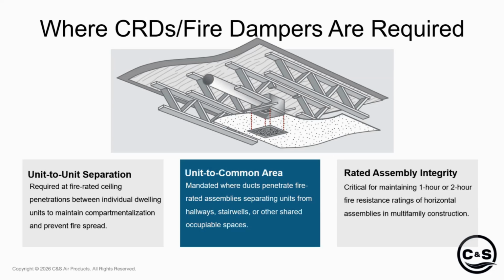rather than just an open space up there in the opening, which we've gone back and tested with UL a lot over the years. We've actually run a radiation damper test where you put a floor ceiling assembly up over a furnace with no damper in it, so just an opening. And I think the test lasted 40 minutes before we called it. So ceiling radiation dampers add, I don't know, something like a 40% additional lifespan. So the fire department can come, put the fire out, and let people have additional time to get out of the building in the case of a fire. So they are important.